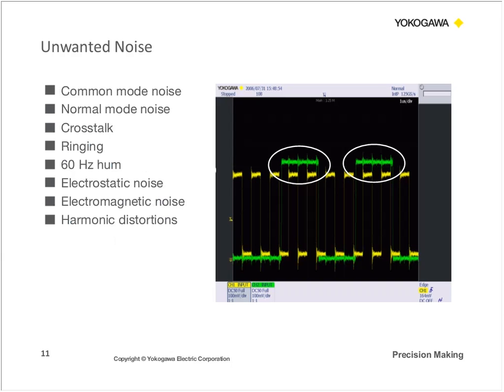Now, another concern that we don't always immediately think of is unwanted noise. I've listed on there all the noise that we can typically see in our measuring instruments. This includes not only common mode noise, but also normal mode noise. As far as temperature data acquisition is concerned, you can have crosstalk, maybe some power line 60 hertz humming, or ringing as we like to call it. There's also electrostatic and electromagnetic noise that can occur when you are dealing with industrial type environments. So we'll be taking a look at how isolation can be used to not only measure these problems, but also get rid of them as well.